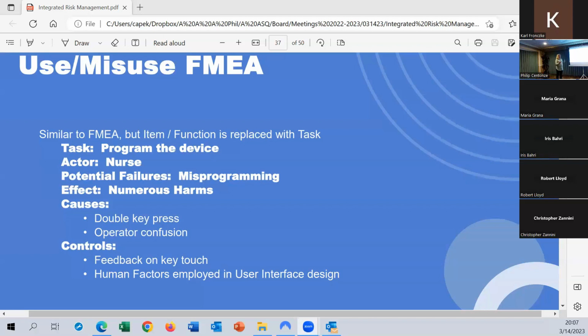FMEAs come in a lot of different flavors. You can have a design FMEA, and you can have a use FMEA, which looks at the way the user is going to interact with the product and determines ways that use errors can occur. In the use FMEA, we analyze the task, who's doing the task, and how the user can fail to perform that task. A lot of times you hear the word user error.